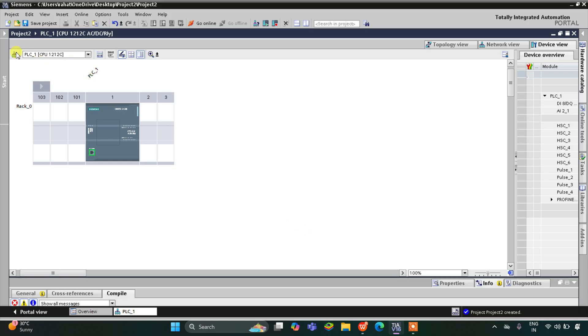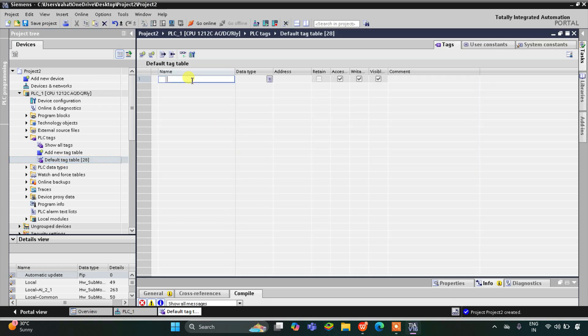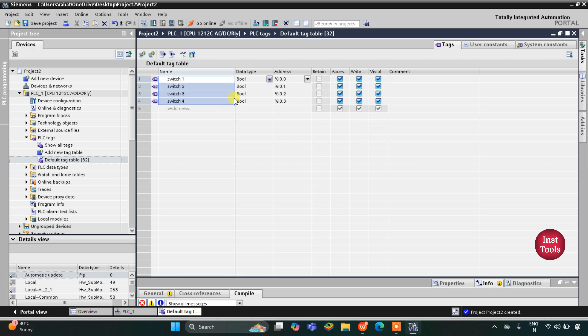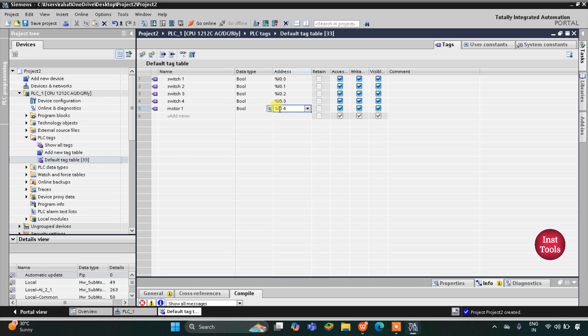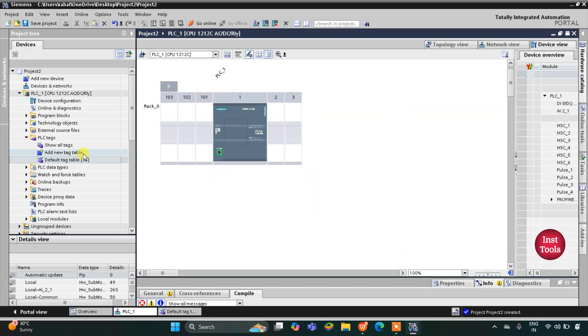This is the interface of TIA Portal. Let's go to PLC tags, default tag table. We have four switches, so let's write switch 1, then click on the corner and drag it to 4 — switch 2, switch 3, and switch 4 will be automatically fetched. Then I'll add the outputs: motor 1, and I'll change the address to Q0.0, then drag to 4 so motor 2, motor 3, and motor 4 are automatically fetched. Let's minimize this and go to program blocks.